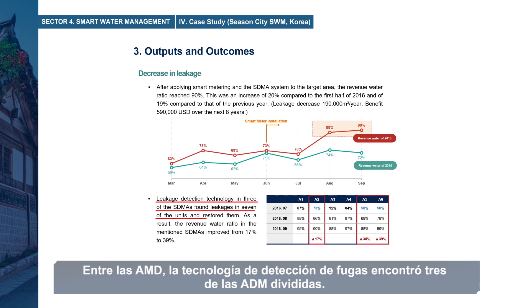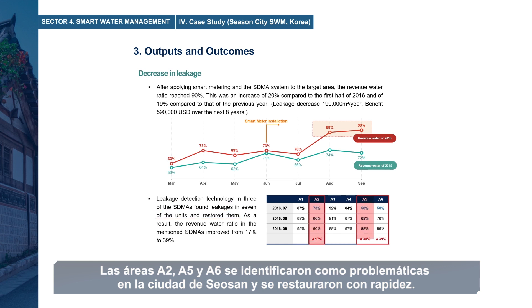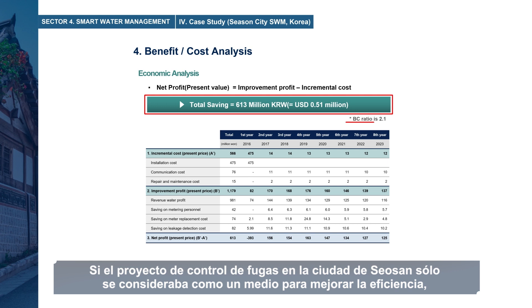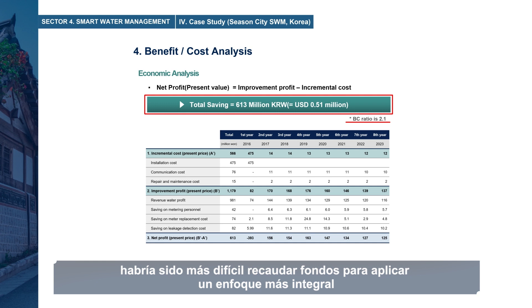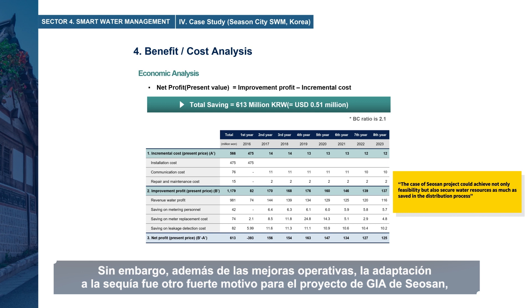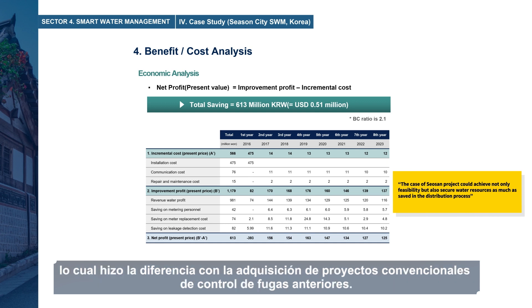Among the sub-DMAs, leakage detection technology found that three of the divided sub-DMAs — A2, A5, and A6 — were identified as problematic in Seosan City, and these were restored quickly. This project was implemented with investment from Seosan City and the Central Government's Drought Budget Package. If the leakage control project had been regarded only as a means to improving efficiency, it may have been more difficult to raise funds. However, in addition to operational improvements, drought adaptation was another strong reason for the Seosan SWM project, making it different from previous conventional leakage control projects.